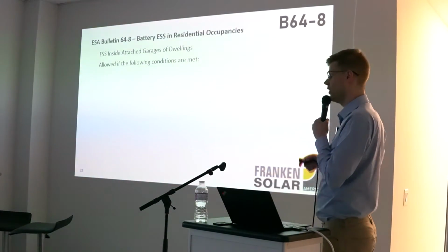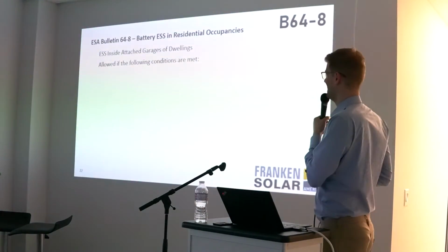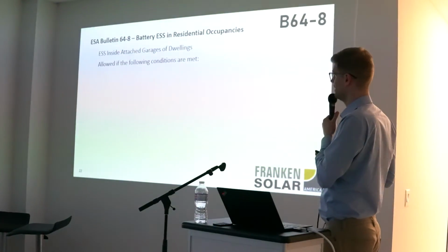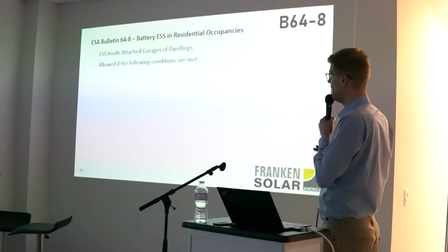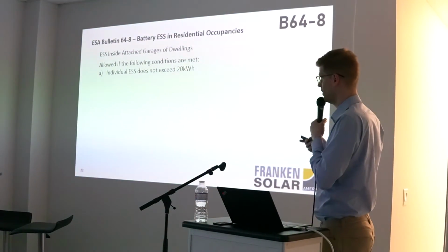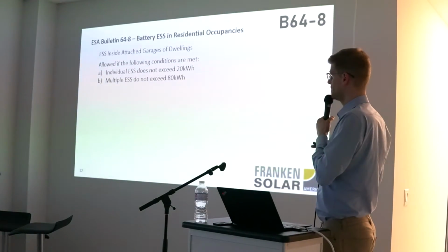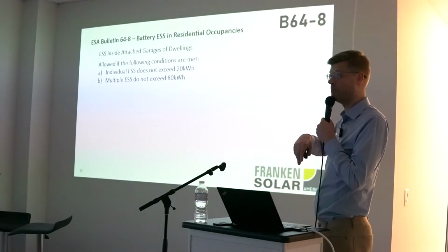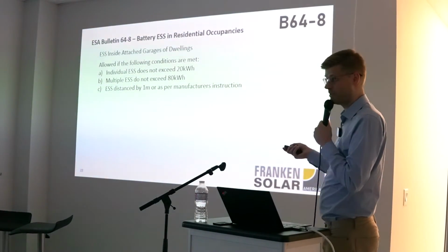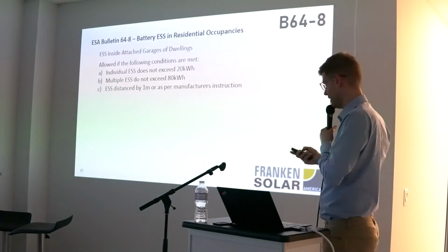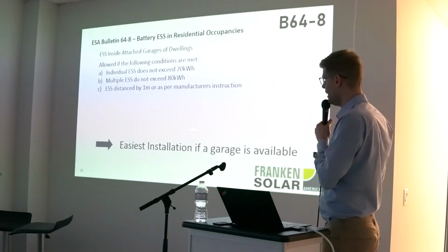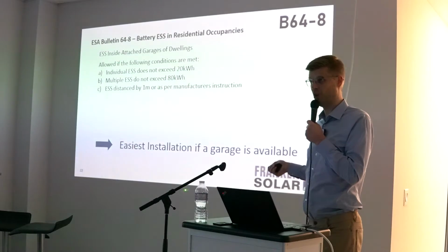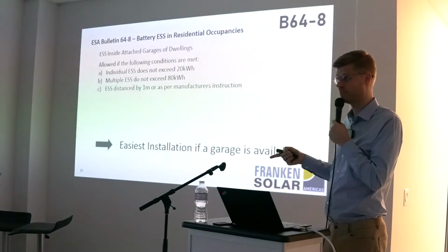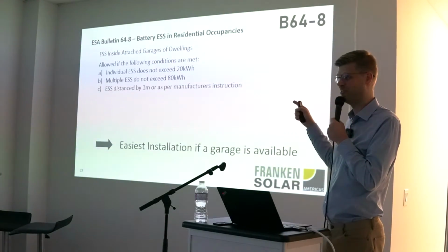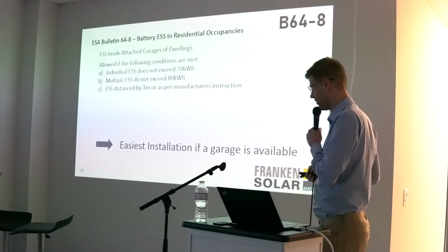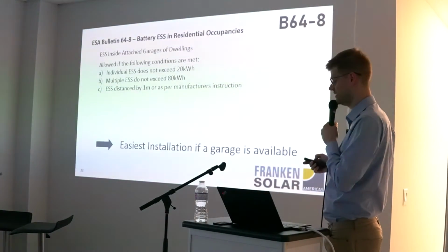There's another option. If you don't want to install it in your basement or in that residential dwelling directly, you can use the attached garage or detached garage, same thing. If you meet the following criteria, very similar to what you already heard. A single system cannot exceed 20 kilowatt hours. Multiple systems, in this case, because it's separated, can go all the way up to 80 kilowatt hours. Same distance requirements, either 1 meter if it's not specified, or you can align them if it's actually tested and specified by the manufacturer. And if you have a garage available to you, this is by far the easiest option for you to go with, because that does not require a deviation request, and has the least amount of hoops to jump through for interconnected fire alarm or smoke alarm and all these requirements we had for the deviation request.